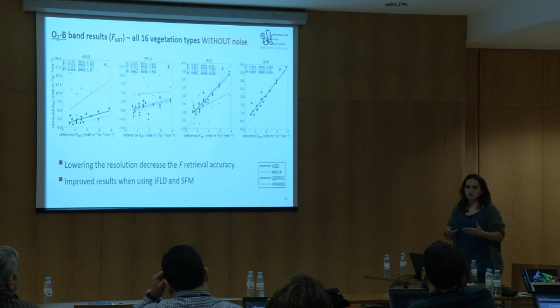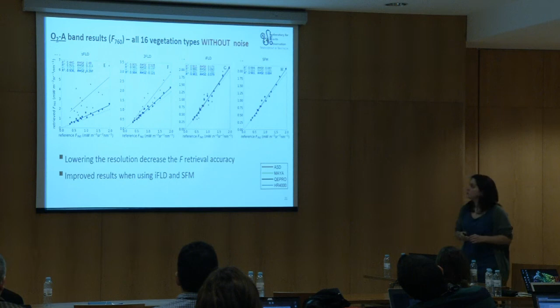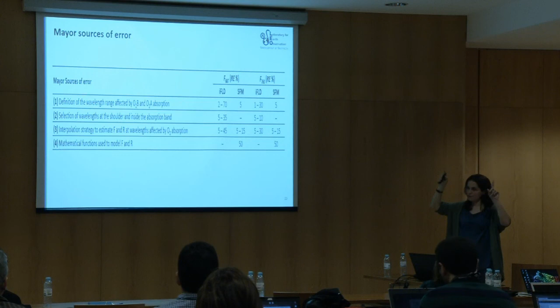Basically, what has been explained before by Javier: if you have a shape in your spectrum and you always define a specific wavelength inside the absorption band, then you are going to make a mistake. So always look for the minimum value in the irradiance. And the same for the channels outside. Depending on the resolution of the spectrometer and also the noise of the spectrometer, you will define these points outside the absorption band, so don't use a fixed value. First look at the spectrum that you have, see where the absorption band stops, and try to choose these points as close as possible to the absorption band.